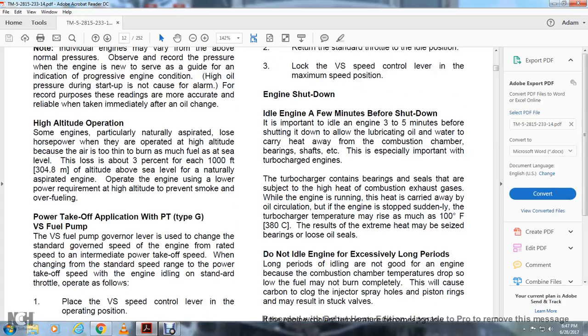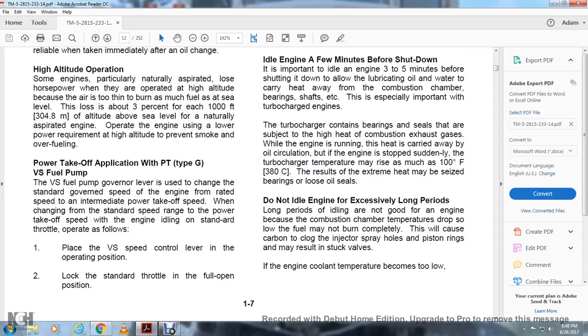High altitude operation. Operating some engines, particularly naturally aspirated ones, loses horsepower at high altitude, because the air is too thin to burn as much fuel as at sea level. The loss is about 3% for each 1,000 feet of altitude above sea level. Operating the naturally aspirated engine at lower power for the high altitude requirement prevents smoke and overfueling.